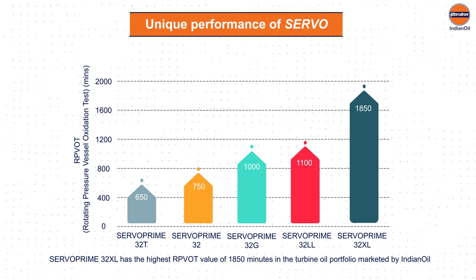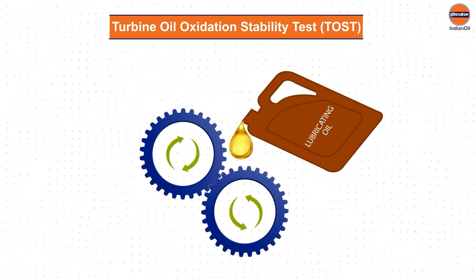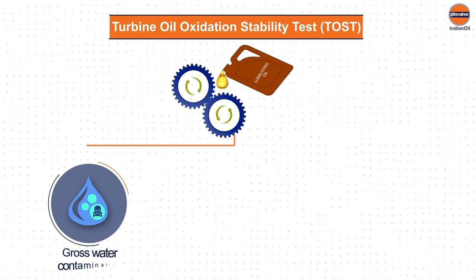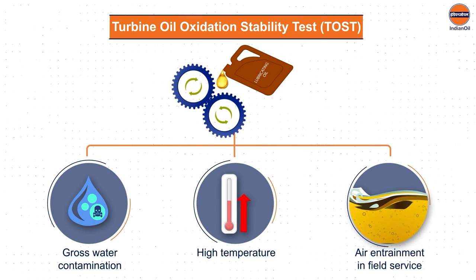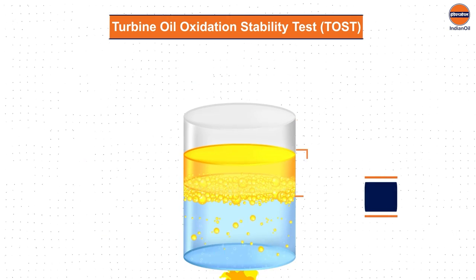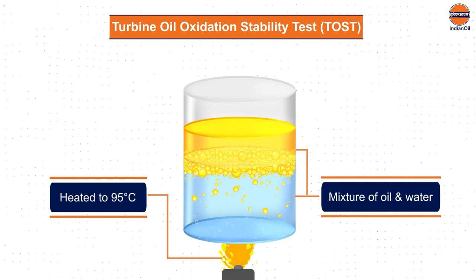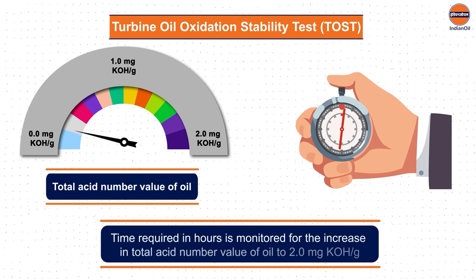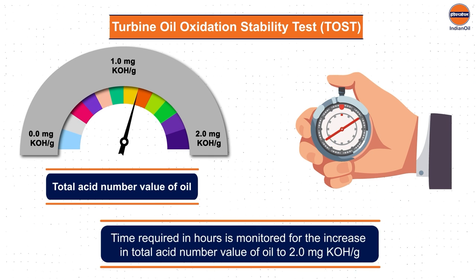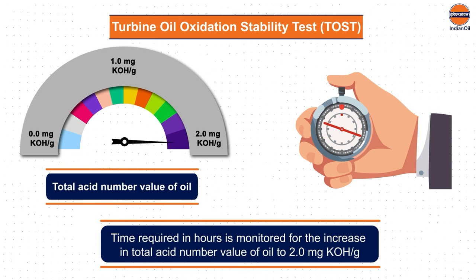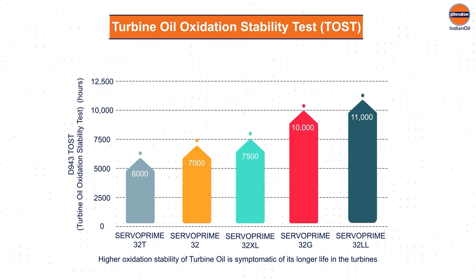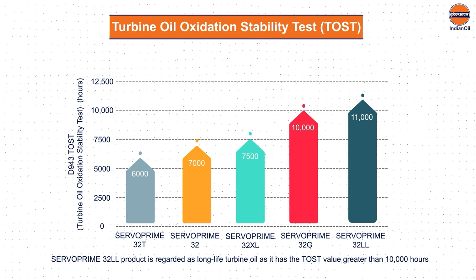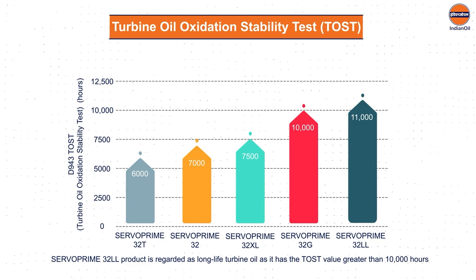Next is the Turbine Oil Oxidation Stability Test (TOST), used to indicate oil life for lubricants continuously exposed to gross water contamination, high temperature, and air entrainment in field service. In this test, a mixture of oil and water is heated to 95°C in the presence of a catalyst and oxygen to simulate severe oxidation. The time in hours is monitored for the increase in total acid number to 2.0 mg potassium hydroxide per gram. Servo Prime 32LL is regarded as a long-life turbine oil as it has a TOST value greater than 10,000 hours.